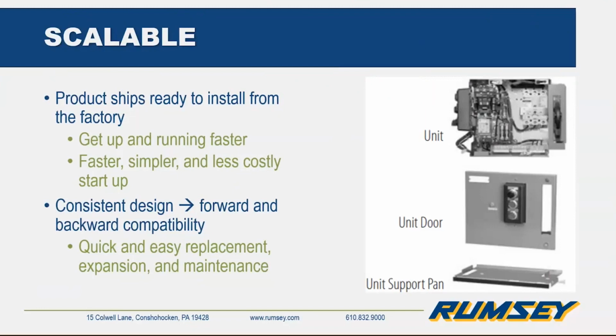There are certain things to look for and be cautious of, but one of the things we'll ask for first when you're looking to get a new bucket or unit is the serial number of the existing MCC. With that, we can look up all the necessary information to make sure it's truly compatible. So with the exception of SecureConnect units, mixing old and new equipment can pretty much be easily achieved as long as everything is looked over properly.